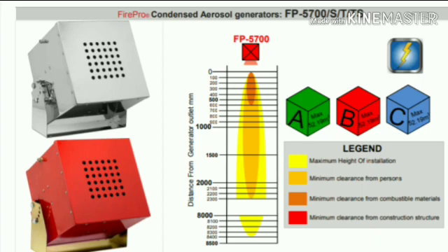Next generator is FP-5700 S, T, and TS. Activation line supervision current maximum: 5 mA. Aerosol discharge time: minimum 15 seconds, maximum 20 seconds. Generator dimensions: height 300 mm, width 300 mm, length 300 mm. Self-activation temperature of FPC: 300 degrees. Class of fire: NFPA 2010 ABC. Generator coverage constraints: minimum height 0.45 m, maximum area 32 m². Maximum height of installation: 8.4 meters. Minimum clearance from person: 2000 mm. From combustible materials: 600 mm. From generator casing: 6.4 mm.